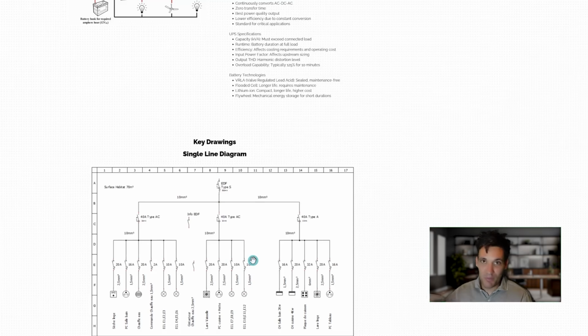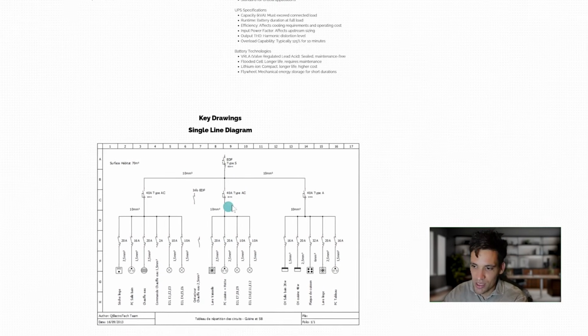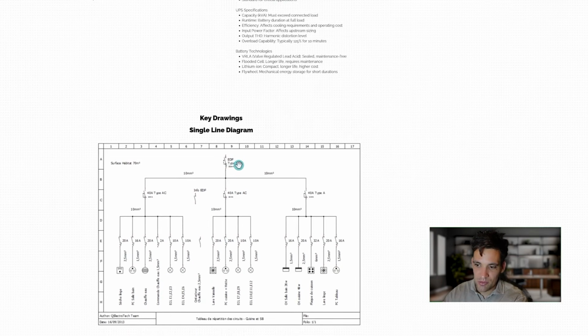With complex systems, you might have multiple drawings. If it's a simple system, it might just be on a single drawing. So this is how a single line diagram looks. You can see there's an incoming supply with a circuit breaker. There's some sort of main switchboard or bus bar that distributes this. You've got 3 circuit breakers connected to this. Then you have distribution boards with the final loads connected to them. So you can see in this system, there's a main switchboard and 3 distribution boards, and you can see which loads are connected to each distribution board. This is essential for showing how the system's connected, where the incoming cabling is connected, how many distribution boards you need, what circuit breakers go in those distribution boards, and where each of the loads are connected.